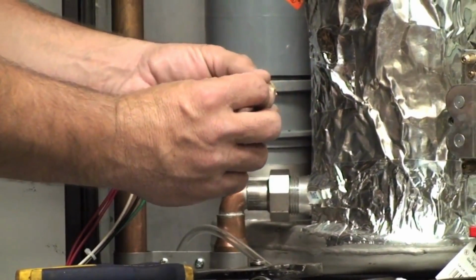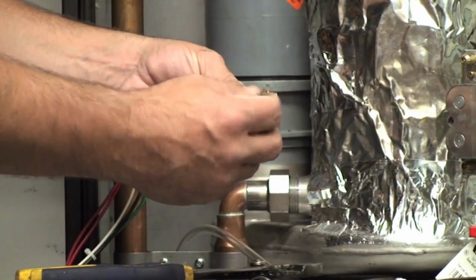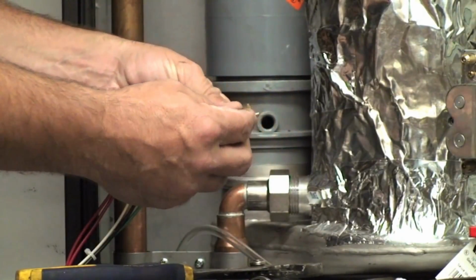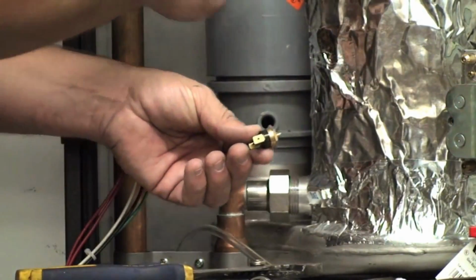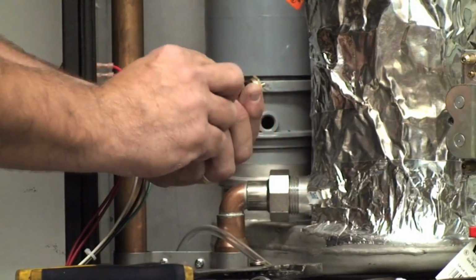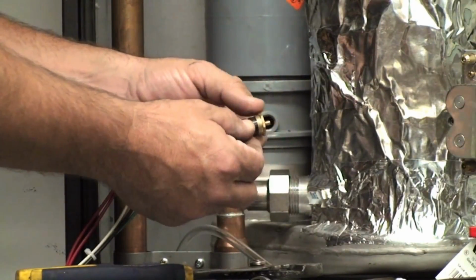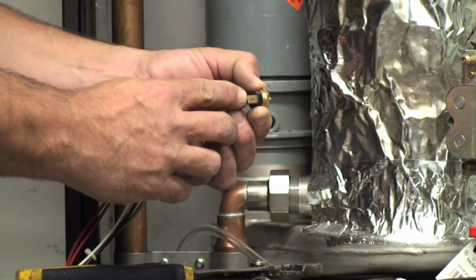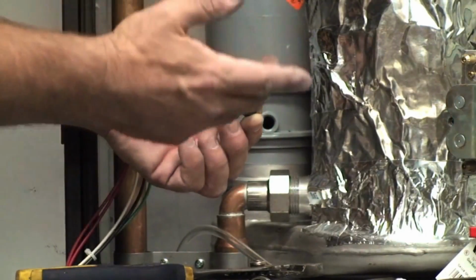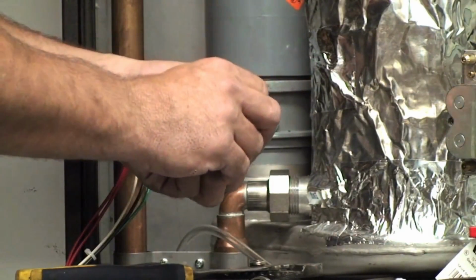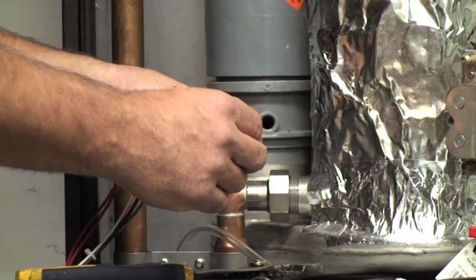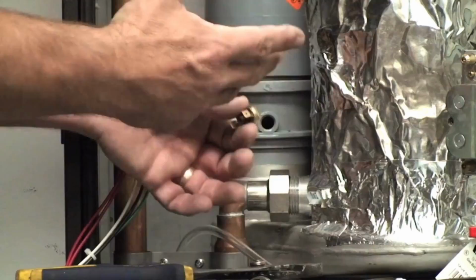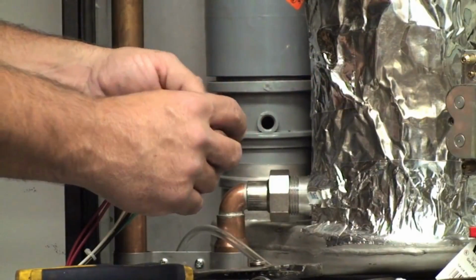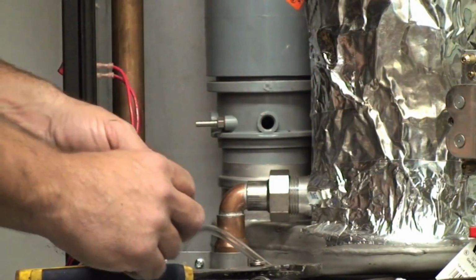And what it does is, it's a bimetallic switch, so if the temperature gets too hot in the flue system, I think these are rated at 210, it'll open and then you simply press the switch to reset it. You monitor the system. If it doesn't reset, then you have to address the situation in your combustion system. It could be cleaning, it could be other issues. So that's another safety we have.